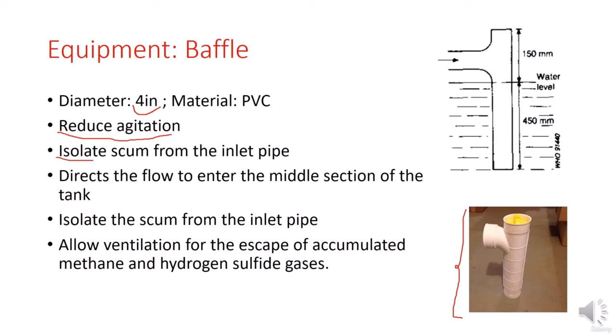A T-baffle will also isolate the scum from the inlet pipe. Without the inlet T-baffle, the flow of incoming sewage would pour on the top of the scum layer, causing that layer to harden and preventing new solids from settling. Instead, solids would build up on the top of the tank and block the incoming flow, causing a serious problem. So basically, the inlet T-baffle redirects the flow to enter the middle section of the tank. The baffle will also allow ventilation for the escape of accumulated methane and hydrogen sulfide gases, getting rid of dangerous and smelly gases.